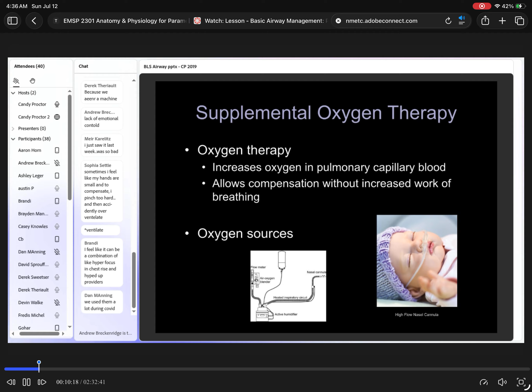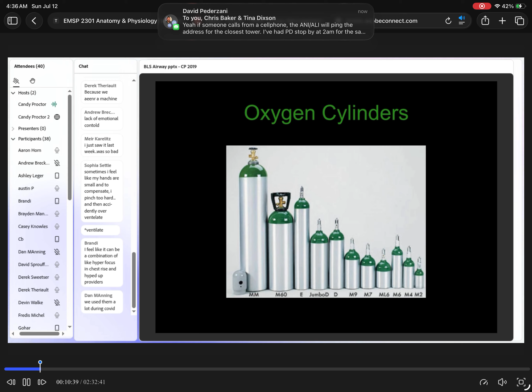What about oxygen cylinders? Again, you should be experts on this. I'm not going to waste a lot of airtime on it, but there are a few choice comments that I will make. We know these things can become missiles. It's oxygen under pressure. We know oxygen supports combustion. Not a good look. And we know we need to have good equipment and test our equipment, make sure everything's working properly. This is a pressure regulator for a portable. What is the most common reason that you get a leak on your O2 cylinder with these regulators? Bad O-ring, exactly. So we need to be able to troubleshoot and fix this problem. It's easy enough to fix.